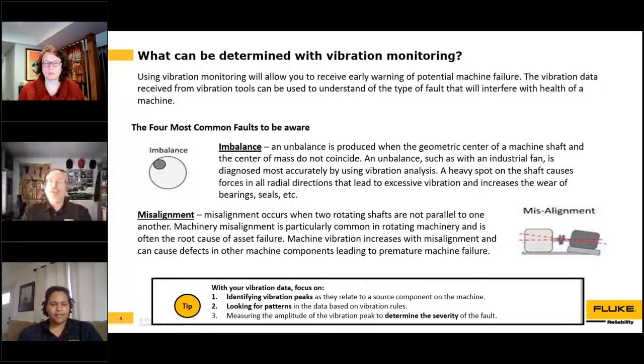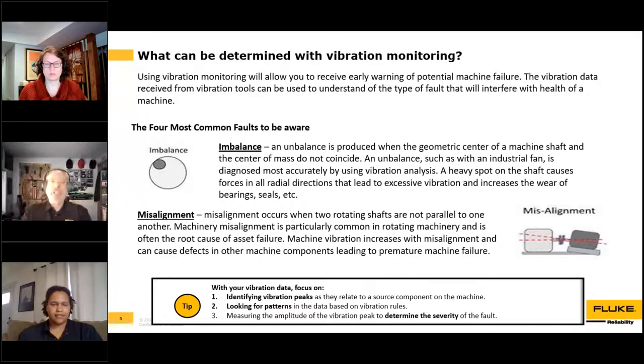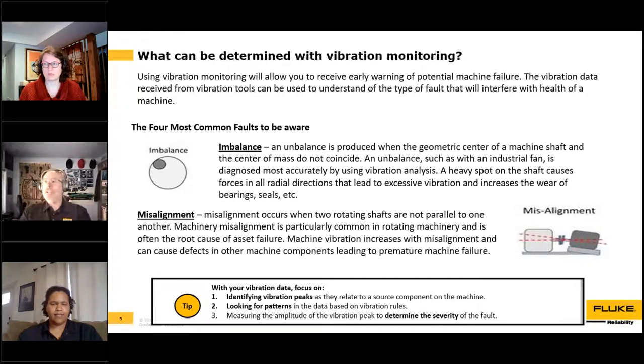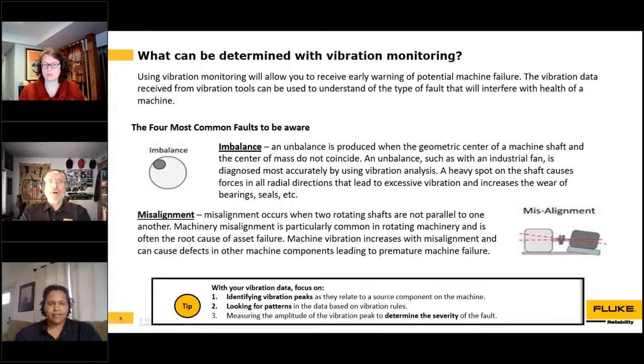Studies have shown misalignment can be responsible for as high as 50% of the faults of rotating machinery. When I was in the Navy, we did what a lot of people do — we ignored misalignment. We figured that if we just slapped the two pieces together, bolted them up, and eyeballed it, that was good enough. But even a little bit of misalignment left in a machine will cause additional load that leads to bearing wear. Misalignment is where your two shafts aren't aligned to each other. Even though people feel that couplings are designed to take up for the misalignment, that's a bit of a falsehood — they do protect the coupling, but the load still transfers to the bearings and seals.